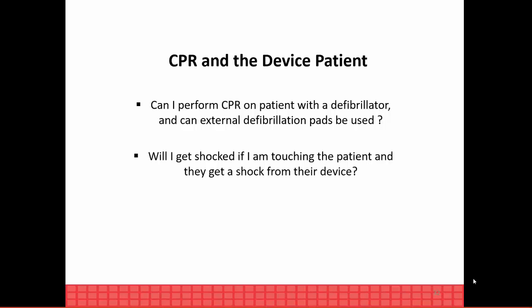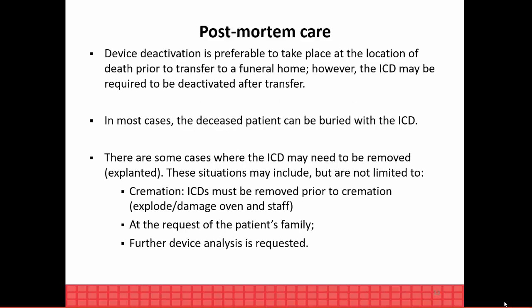It's preferable to use anterior-posterior, but if you can't do that, placing the anterior one as close to the sternum on the opposite side of the device and under the apex of the heart is sufficient. Will I get shocked? We said that yes, you may feel something. It's not going to hurt you. You may feel a sensation, but again, wearing those gloves will help prevent that.